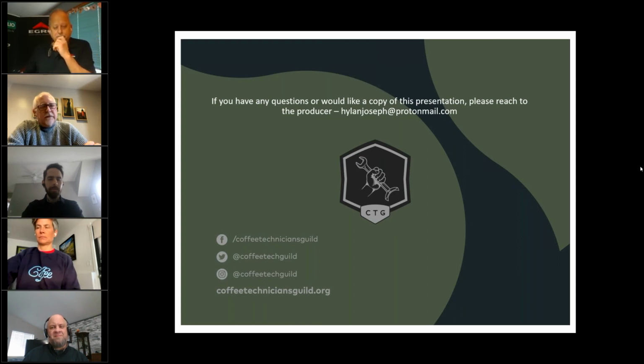Yeah, the phosphates are designed to keep the hard water deposit in suspension as it passes through the brewer. Once it gets past about 185 degrees, the phosphates are no longer able to hold it in suspension, which is why it's not really applicable for espresso machines. You've got to find a different way. And the reason I said one is different, and it's hard to find now because of company acquisition, is that it doesn't use polyphosphate. It uses another compound, which I'm not at liberty to discuss. Anyway, next one. Yeah, you can send me a link because I'm looking for one.